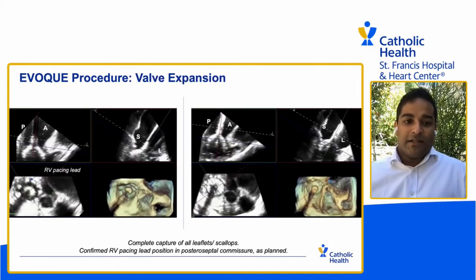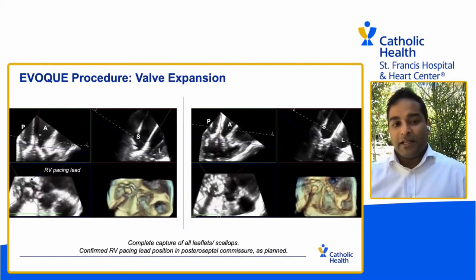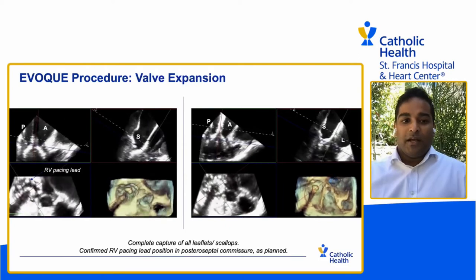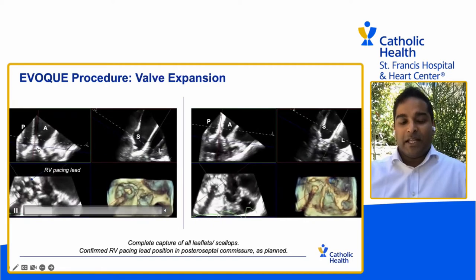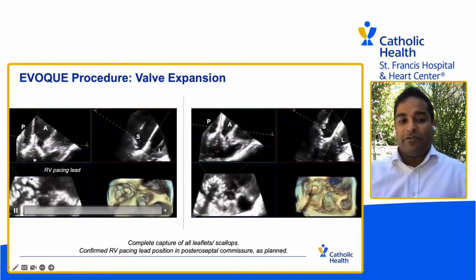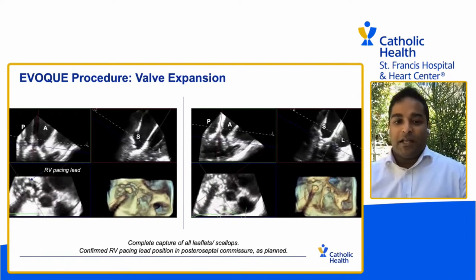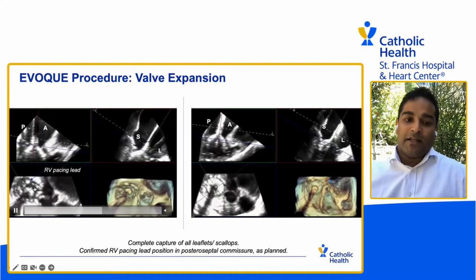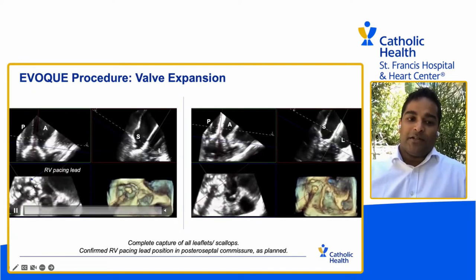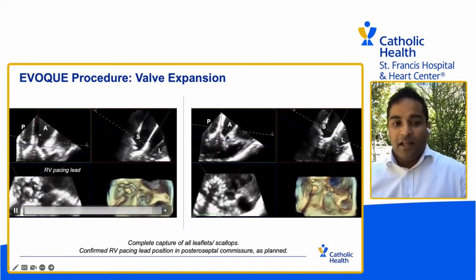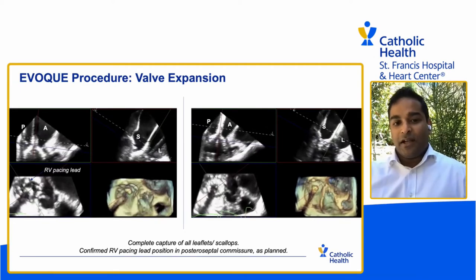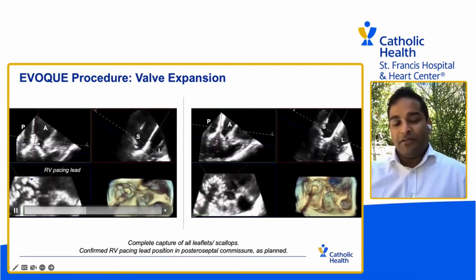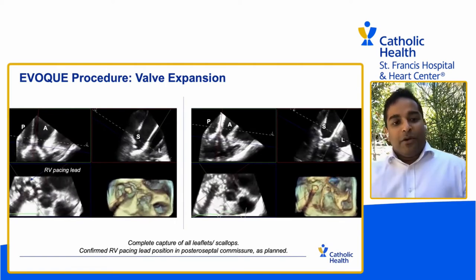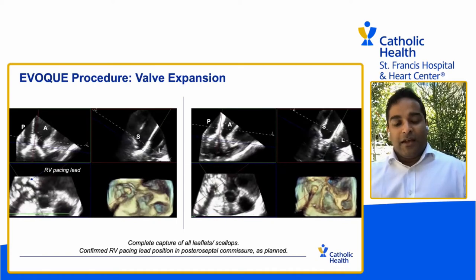Once we're at 90 degrees, we will sequentially deploy those anchors so that they point towards the atria. You can see here that the anchor tips are now pointing atrially, and we've also expanded the ventricular portion of the valve. As we do that, we look carefully at the leaflets to ensure that all of them, in the short axis, are going over the anchor, such that the leaflets are not pinned behind the anchors and are traveling between the anchors and the body of the valve.